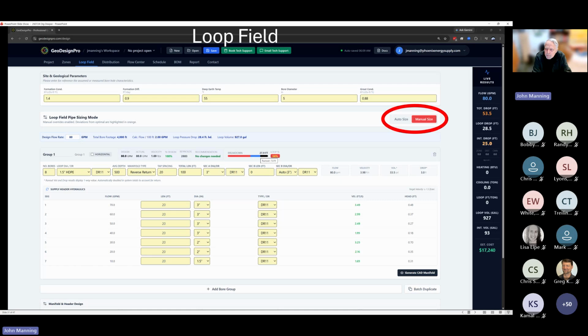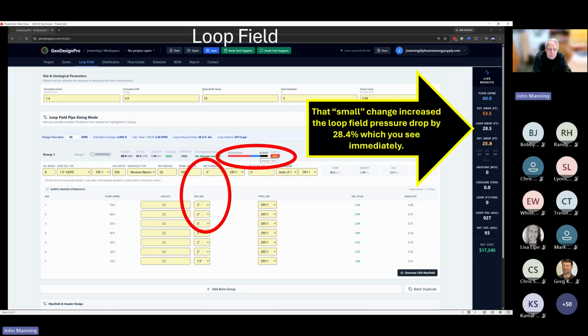And one option you have is a manual mode where you override the auto selection feature. And in this case, we've changed that 4-inch pipe and thought, okay, we're going to save a little money. We're going to go with 3-inch pipe. However, our green indicator for the loop field pressure drop being less than 70% of the total gives you a visual cue that maybe you could do better in terms of pressure drop. And in this case, that small change of changing a few lengths of pipe from 4-inch to 3-inch increased the pressure drop of our loop field by 28.4%, which immediately shows up on the far right of our desktop.